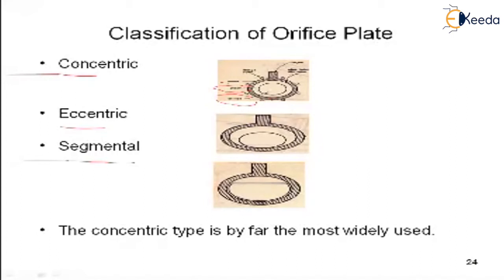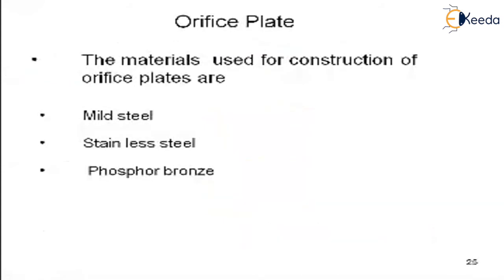In the concentric type, there is a small hole to avoid air pockets. The orifice center and the air pocket hole have a distance between them — that is why it is called concentric. In the eccentric type, the air pocket hole is touching the edge. In the segmental type, the openings are bisecting and overlapping. Among these three types, the concentric type is most commonly used.